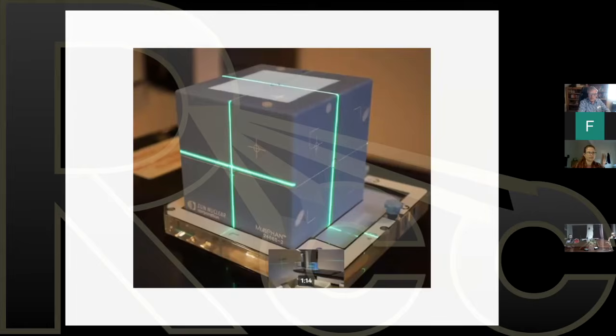Here's one such device. These cubes are very important, and there are several vendors that make these cubes. These cubes have the ability to test a number of different things. So for example, you see here a 10 by 10 field, and there are marks that show you it's a 10 by 10 field, so you can quickly check field size. You can quickly check laser centering here, and here's the sagittal laser. You can check by rotating the gantry that the light field also agrees with the laser.